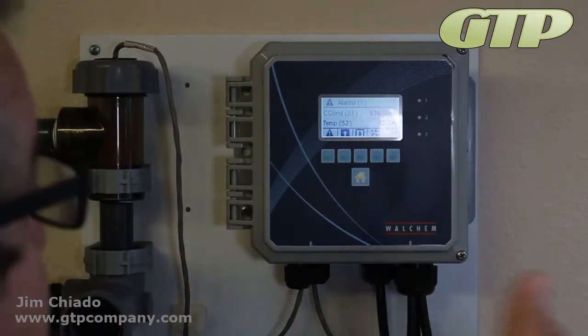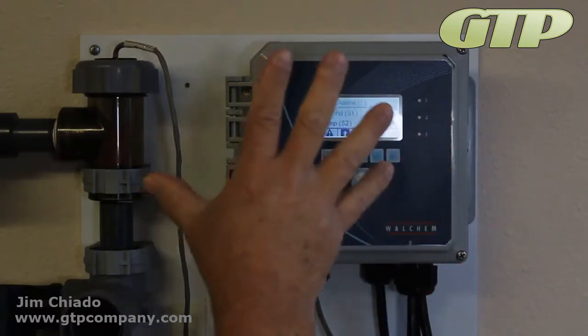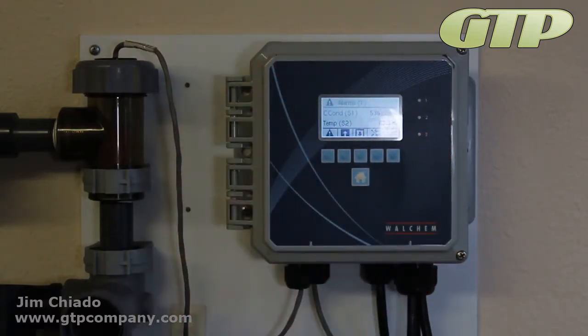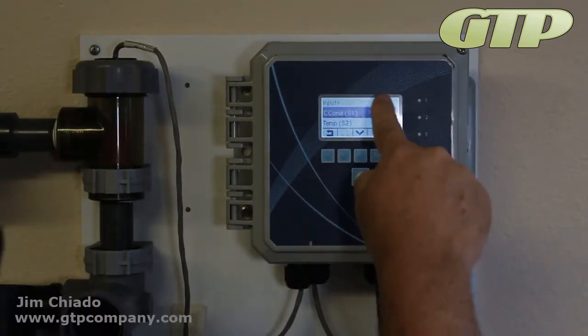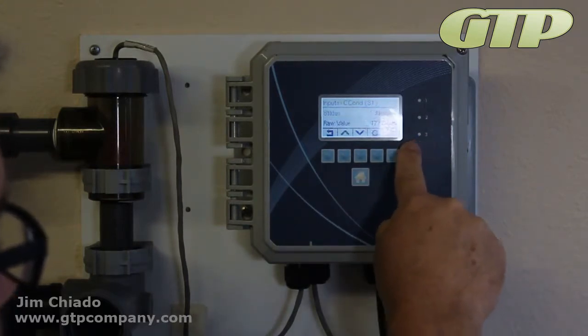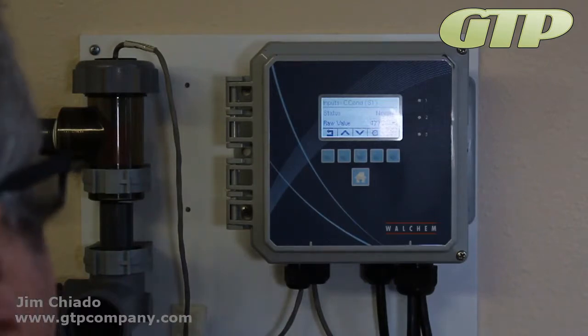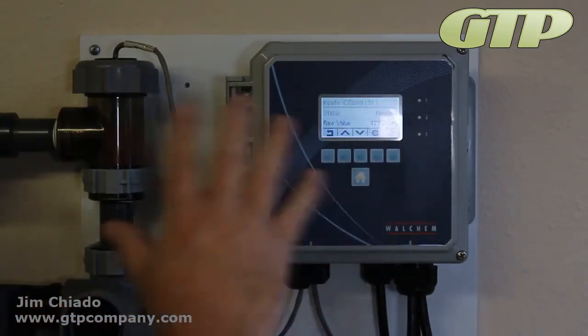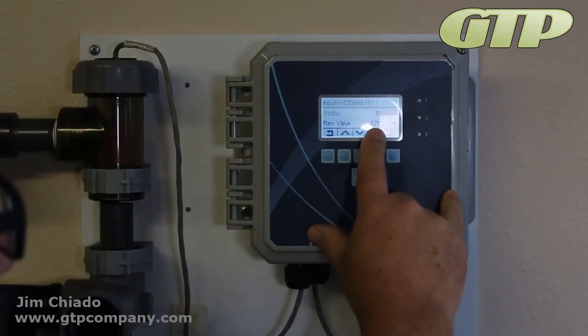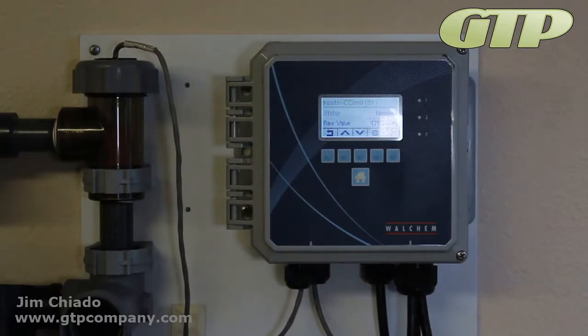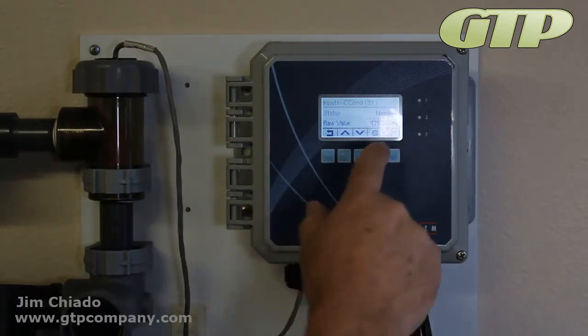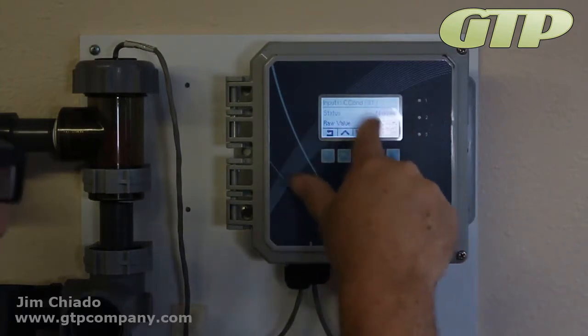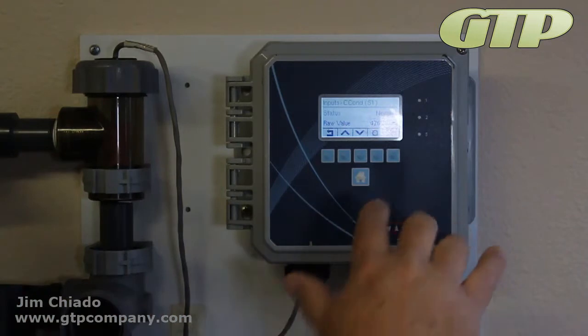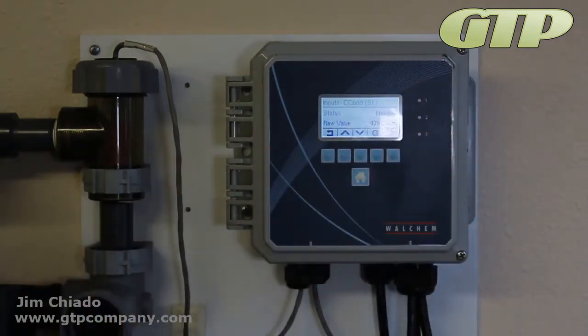So you'll see that in that video. Out of range means that the system can't do the adjustment from what it thinks it is, the raw value, to what you're telling it it is. Now, for conductivity inputs, if instead of hitting maintenance we hit raw value, we see it says 477. The machine can do at least 1.5 times, so half of that, 225, plus that, it'll go up to about 625. So you see what I mean? It knows this, and you can't change it. It thinks it's 476, and I can only do 1.5 times plus or minus from what it thinks it is.